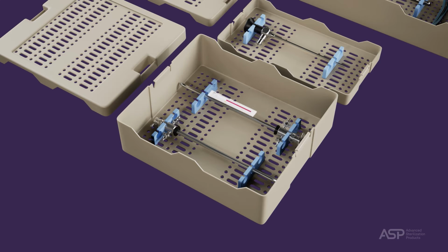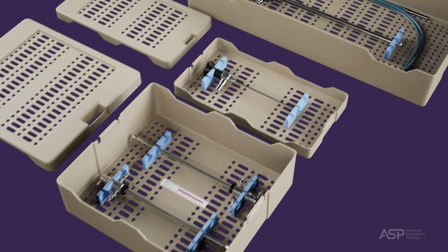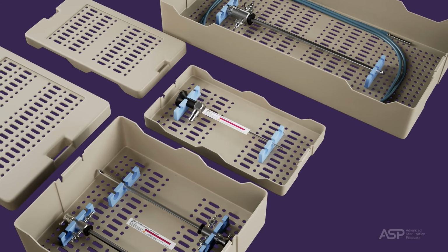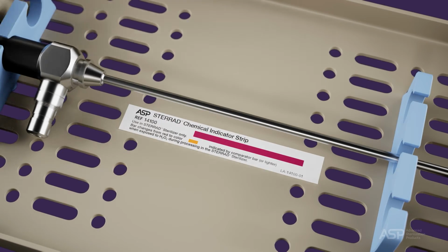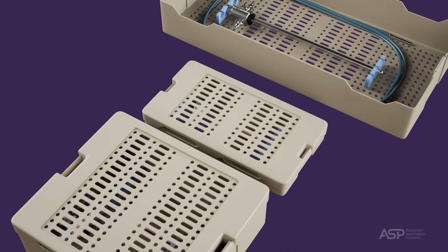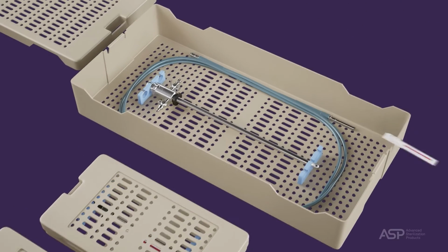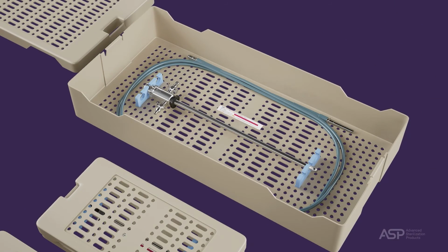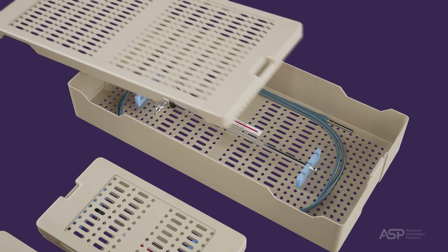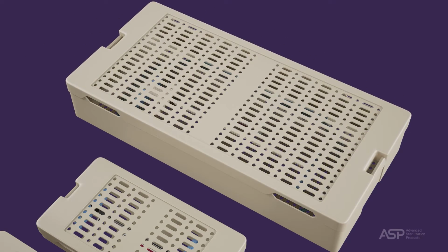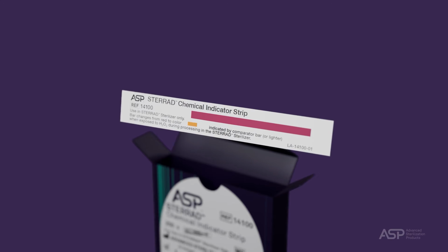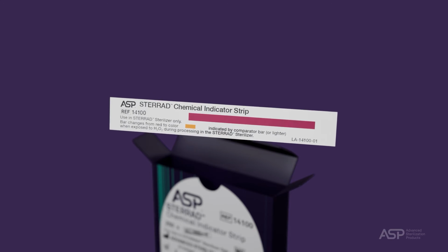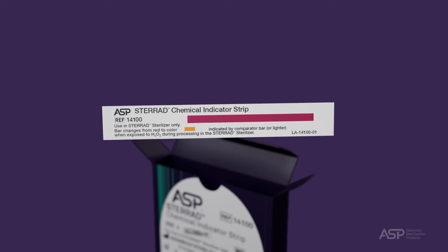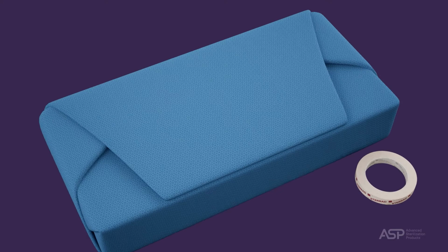The STERRAD chemical indicator (CI) strips must go into each individual tray container or pouch and in the center of each package to be processed in the STERRAD sterilizer. The chemical indicator is your verification that the items in the package were exposed to H2O2 and therefore achieved sterility. STERRAD chemical indicator (CI) strips are not indicated for use with steam or ethylene oxide sterilization cycles.